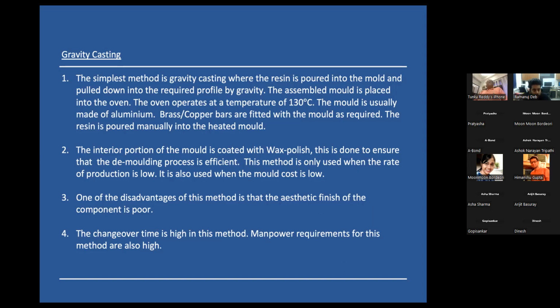It is quite a simple procedure. The resin is just poured into the mold and it's pulled down into the required profile by gravity. After this process, the assembled mold is placed into the oven. The oven usually operates at a temperature of 130 degrees. The mold in this case is made of aluminum, and in the case of inserts, brass and copper bars are fitted into the mold.